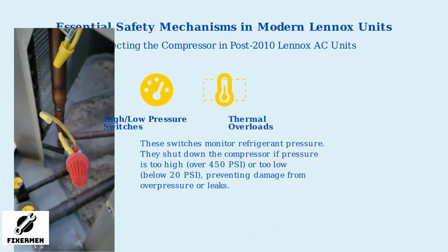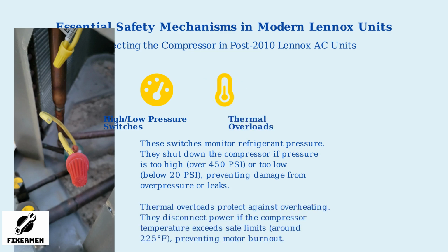Next are thermal overloads, which protect against overheating. If the compressor temperature rises above safe limits around 225 degrees Fahrenheit, these overloads disconnect the electrical power to prevent motor burnout and component damage. Time delays are another crucial safety feature. They add a 3 to 5 minute pause between compressor starts, preventing rapid cycling that causes wear and tear. This helps avoid damage from frequent on-off operations during temperature fluctuations.